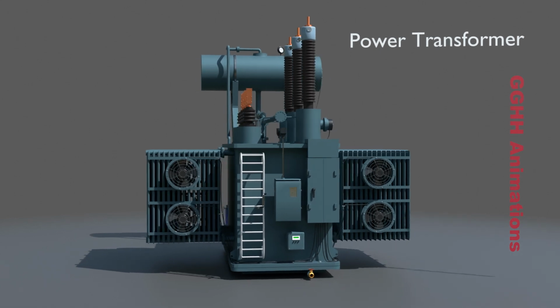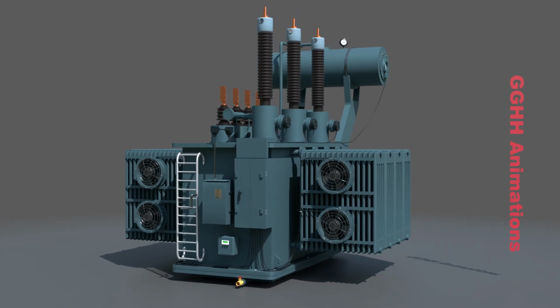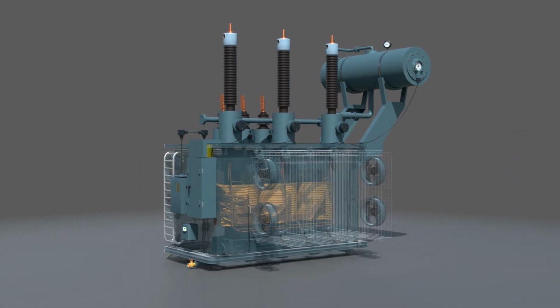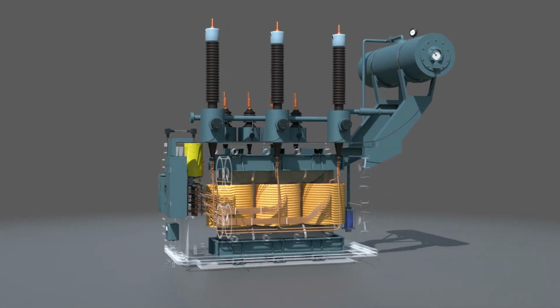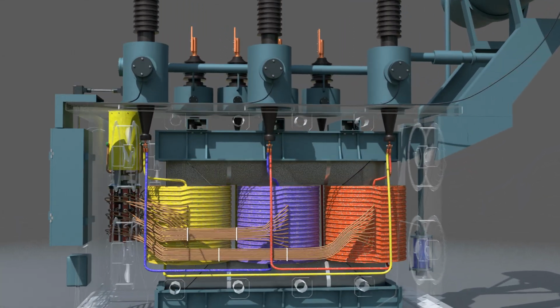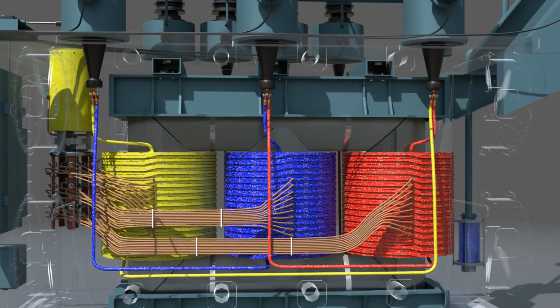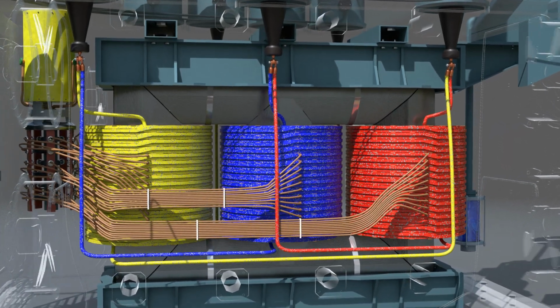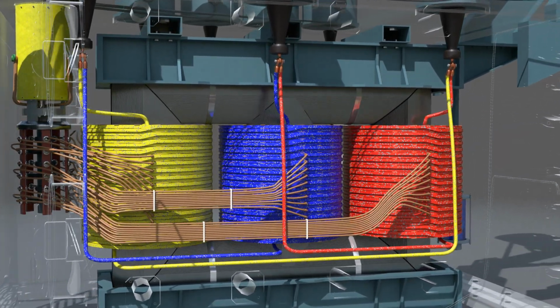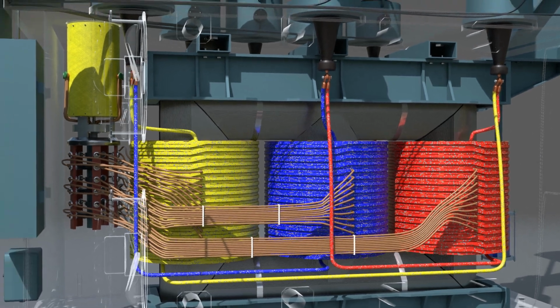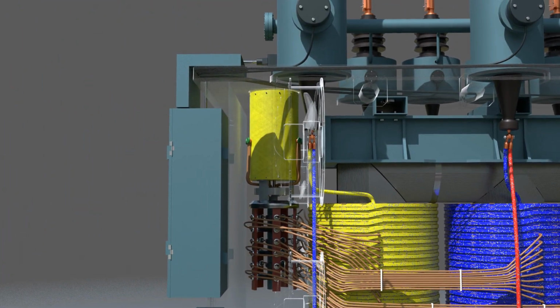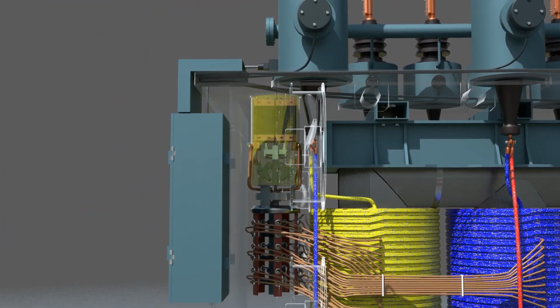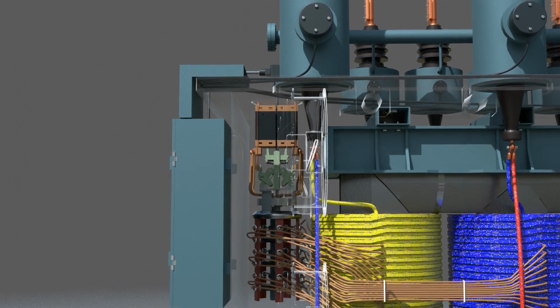A power transformer, an essential part of the electrical grid, helps transfer electricity over long distances. Inside, the core and windings work together to step up or step down voltage as needed. Here's the on-load tap changer, OLTC. It automatically adjusts the transformer's tap position to regulate voltage.